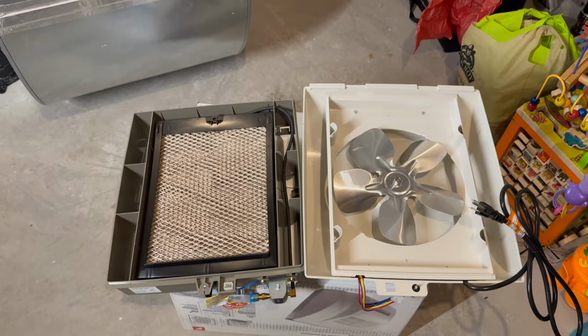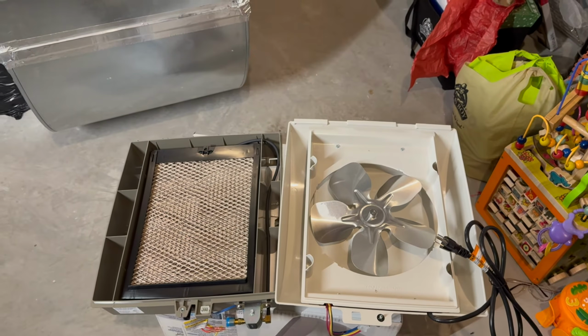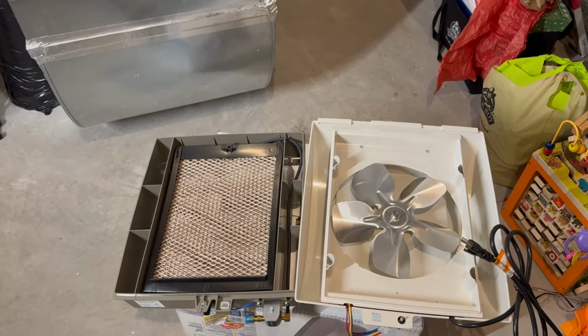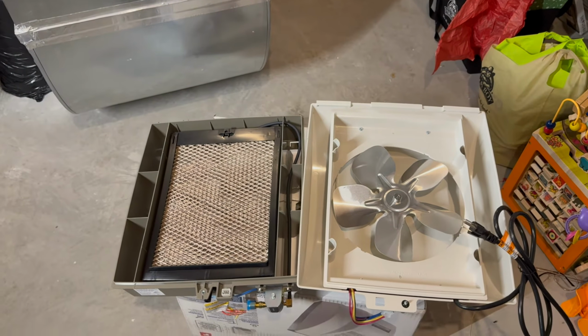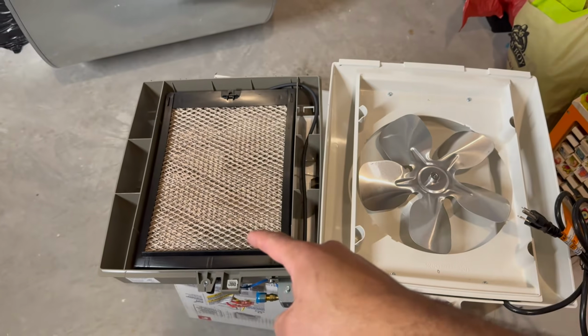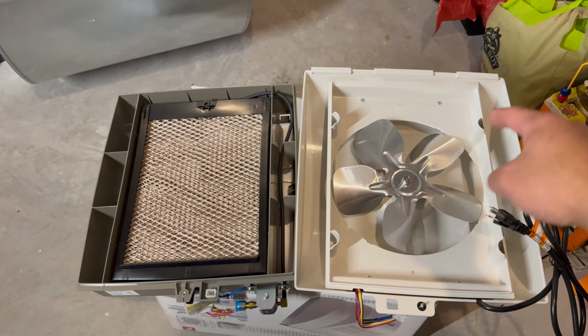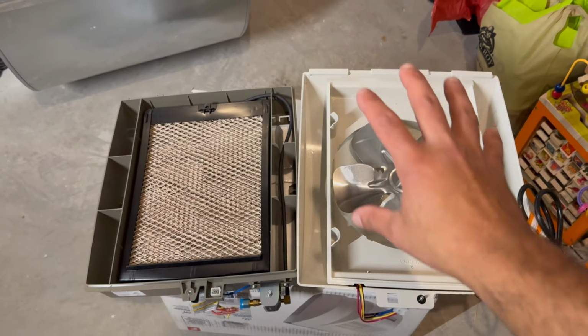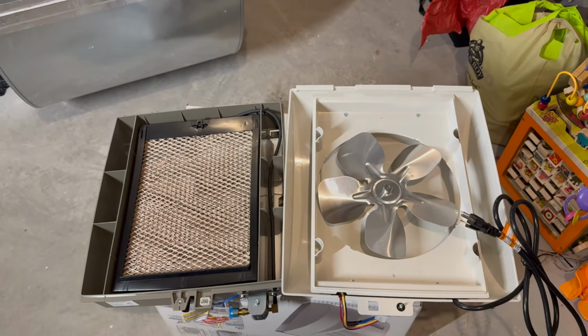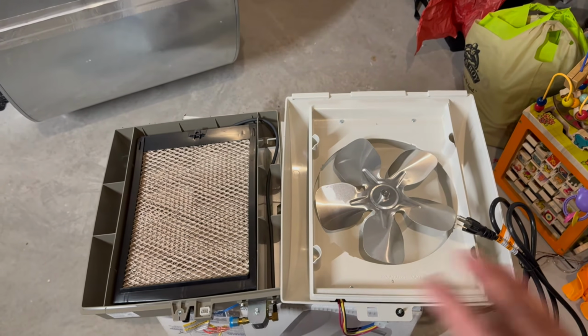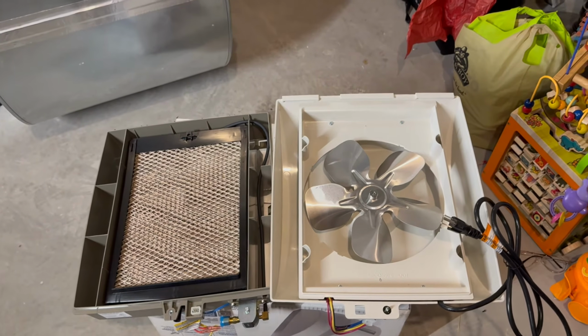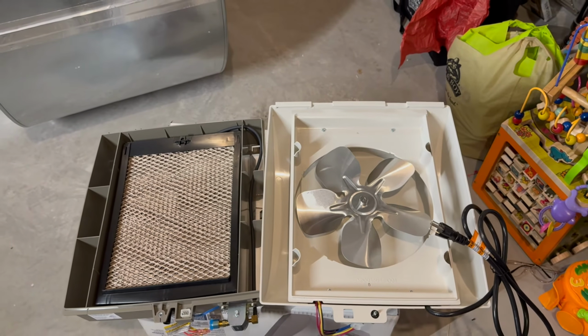So I've split the unit open, and I'd like to demonstrate the difference between a fan-powered humidifier and the bypass. In this case, you have the water that runs through the humidifier pad, and then you have this fan that will blow that humid air right into the supply. So it goes directly into your house. There's no bypass duct, nothing. It's a lot more efficient, and you'll be able to humidify your house a lot faster.